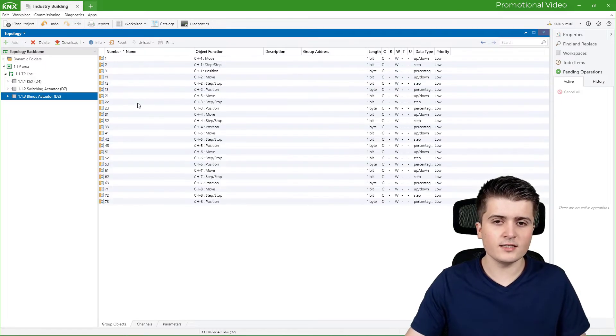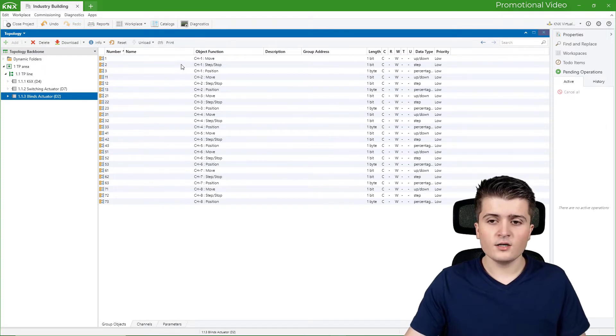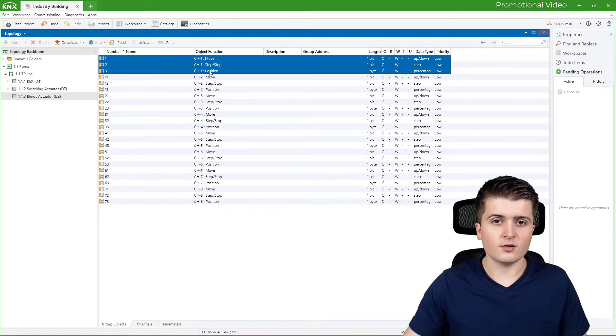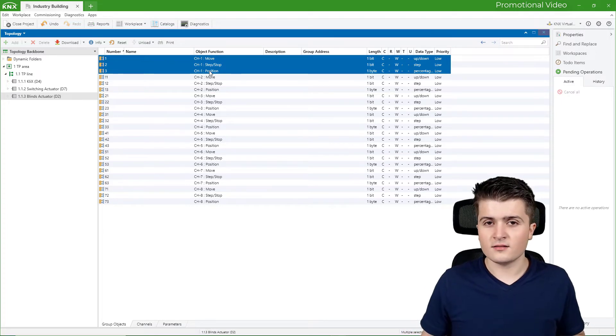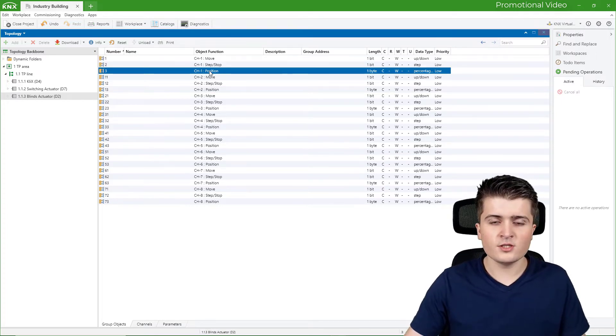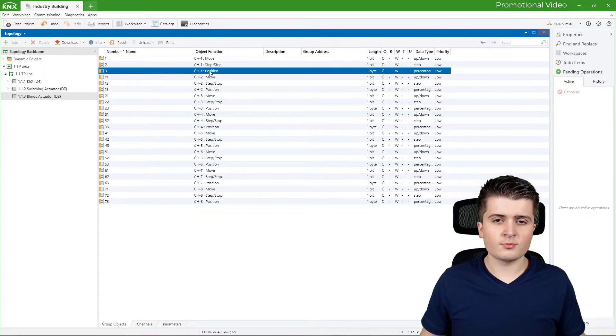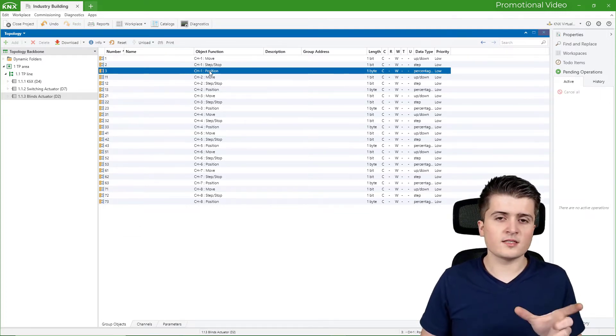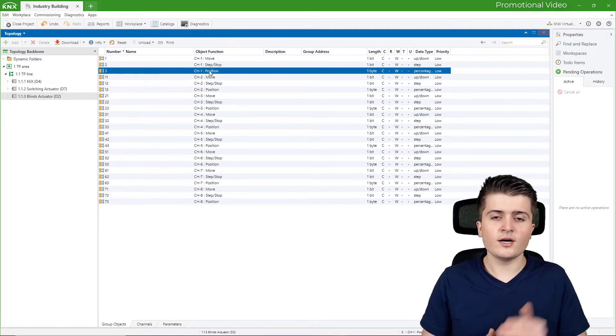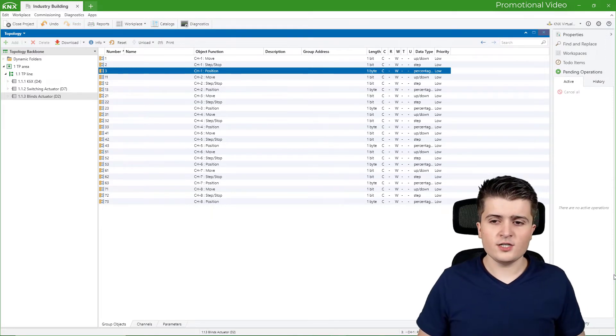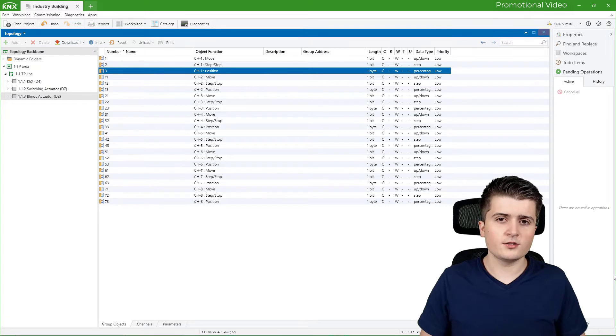Now let's look at the blind actuator. It also has three group objects for channel one: move, step/stop, and position. However, be careful — position here does not mean feedback. Position means you can hook it up to a visualization panel and use a slider to define the exact position the blind should move to. It is the target position specification, not the feedback.